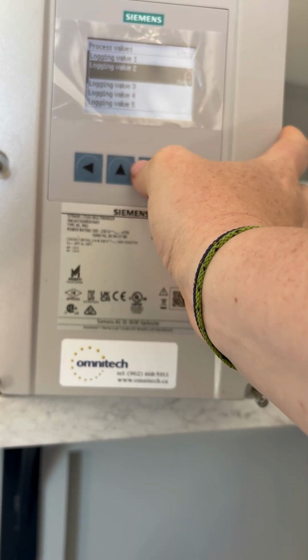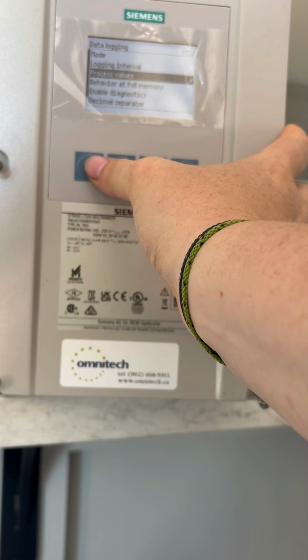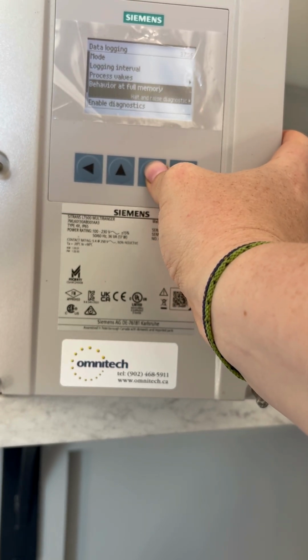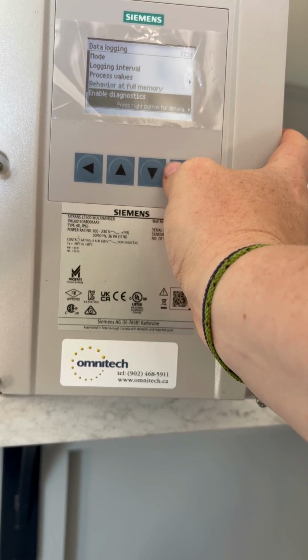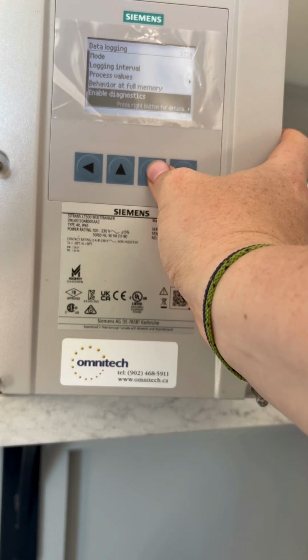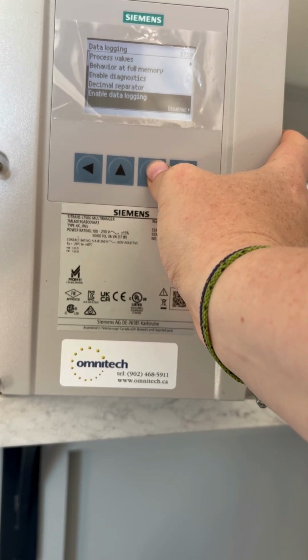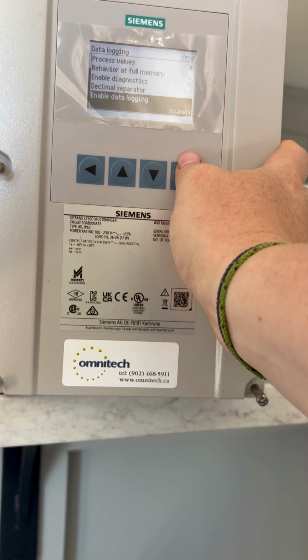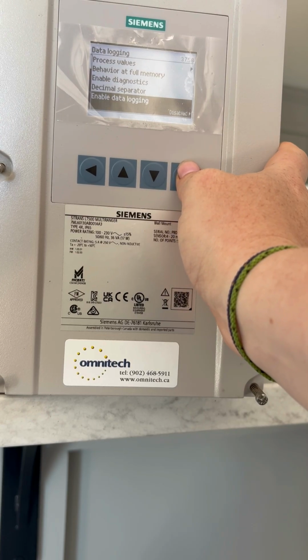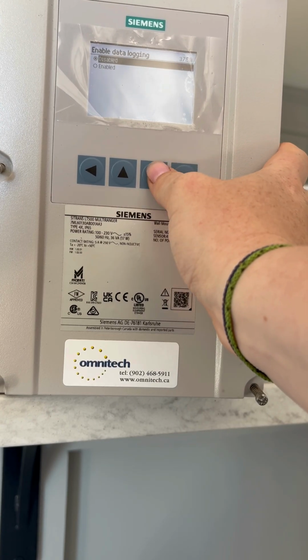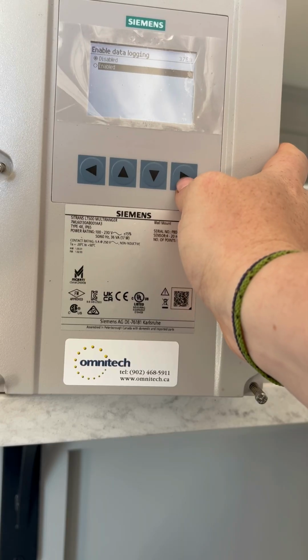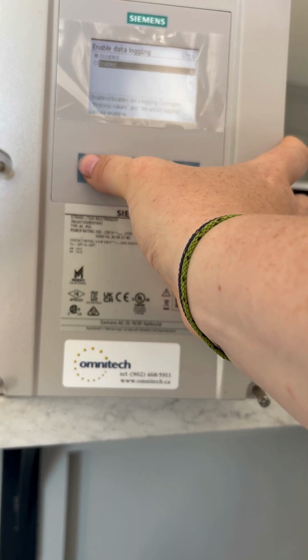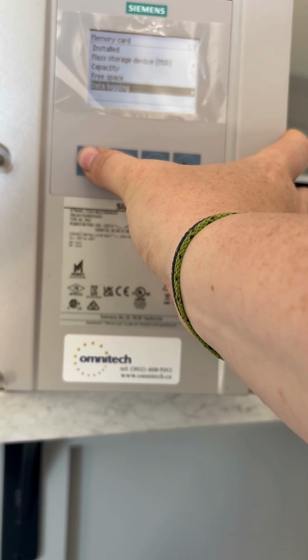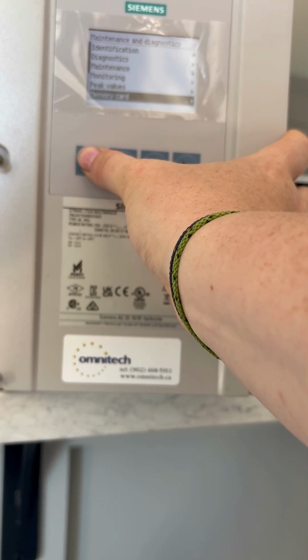So right now I have it set up as level, just 1 value every 5 minutes, and I am not going to enable it until the customer. So this is where I wanted to just let you know that you want to make sure that you enable it. So go down to enable data logging. That's 3.7.5.8. And you just want to click enable and hit the right key. Again, I'm not going to do it because this is a customer's unit. So I'll just keep it disabled. But feel free to go in and enable it when you are starting up.